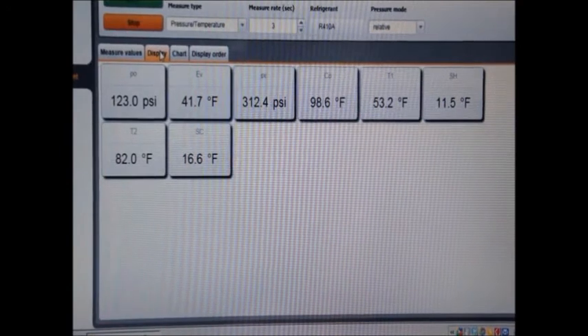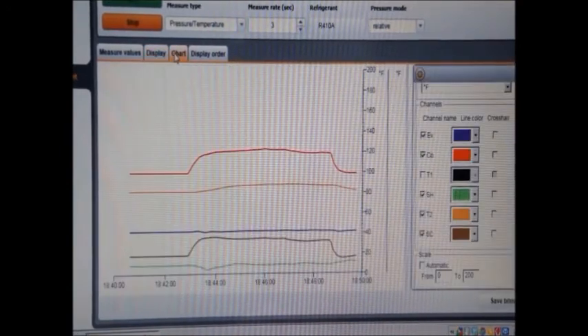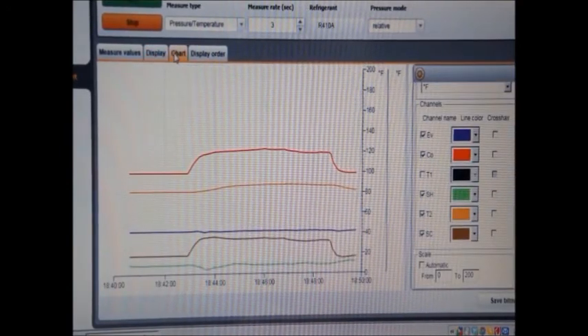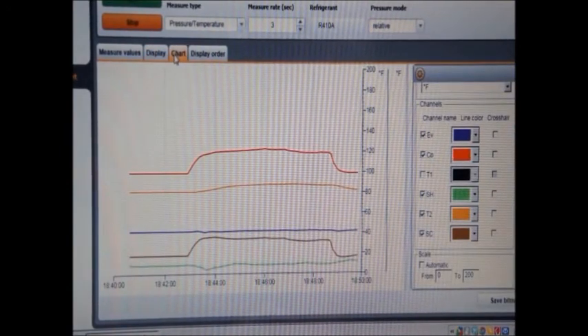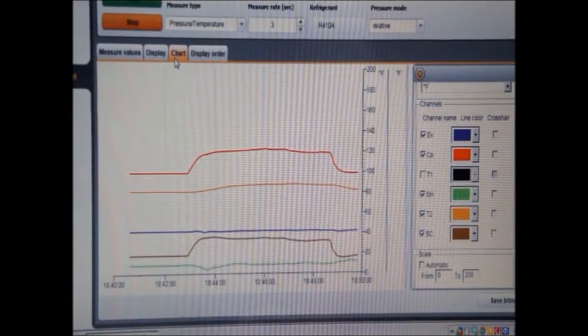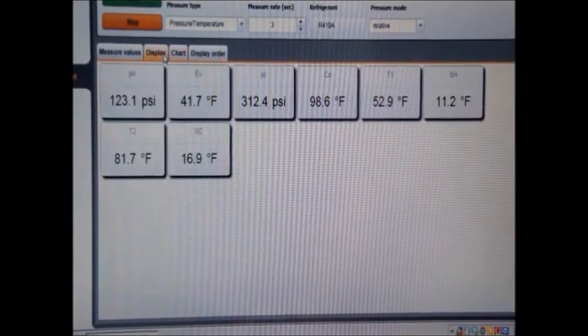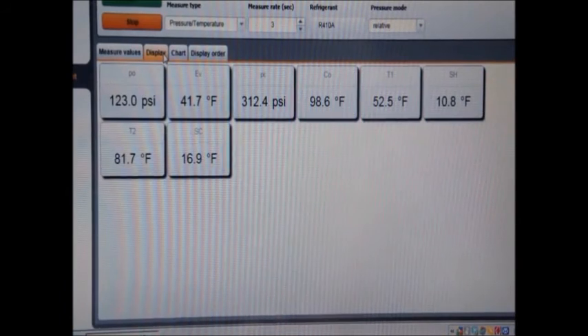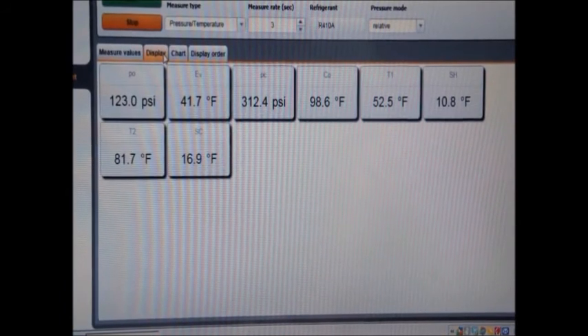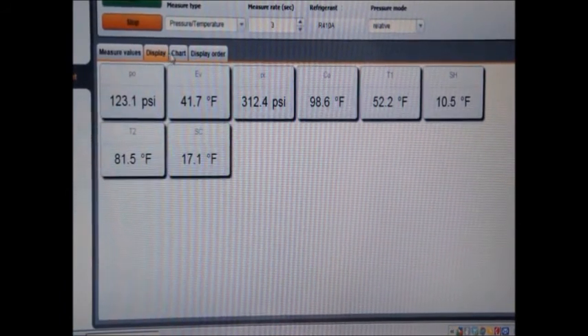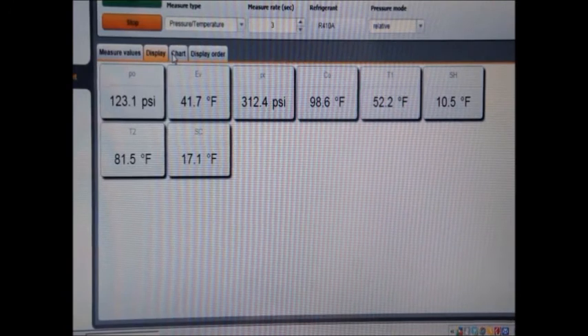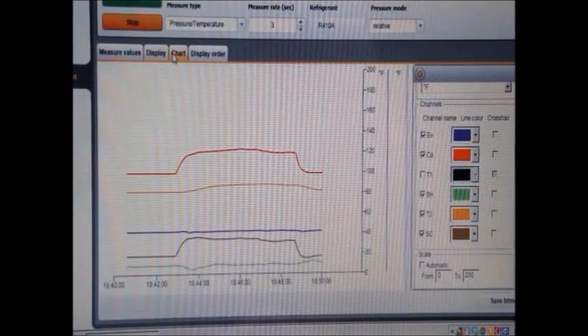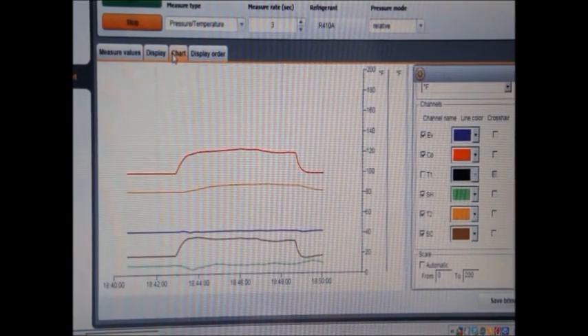Back to the chart, you can see that's all acting pretty normal. On the superheat side, it's pretty much remaining constant. Superheat's running 11.2, 10.8, it's dropping down a little bit right now. But you can see what happened here. It's a pretty interesting characteristic of this unit.